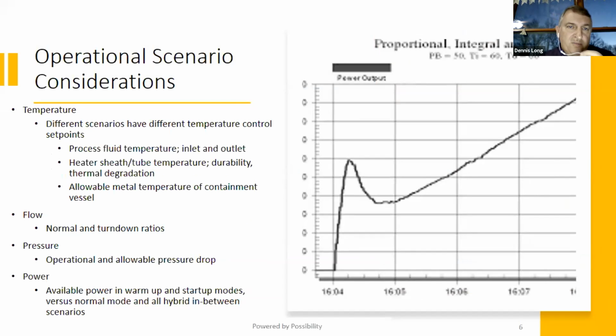If you think about the operational scenario considerations, there are maybe 4 primary areas to think about: temperature, because we have different scenarios with different temperature control set points. For example, the process fluid temperature, the heater sheath and/or tube temperature—looking at those from a durability and thermal degradation standpoint, and also the allowable metal temperature of the containment or pressure vessel. In addition, you could also be looking at flow, because with flow you have normal and turn down ratios, pressure, operational mode, and the allowable pressure drop so you stay within customer needs, and also power—available power, and warm up and startup modes versus normal mode, and a hybrid in-between scenario. So that gives you a pretty good overview of what we're considering here.